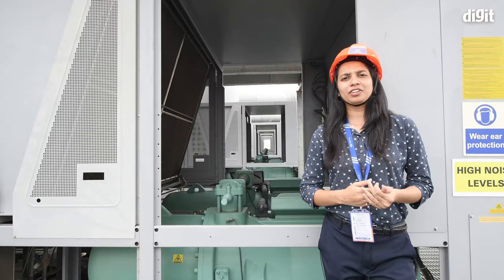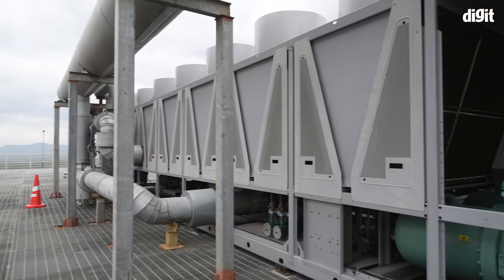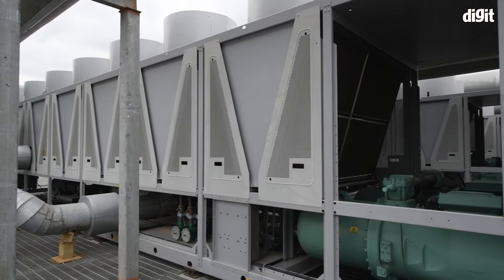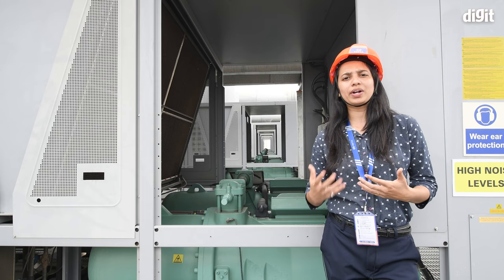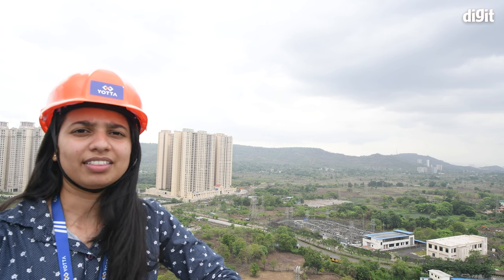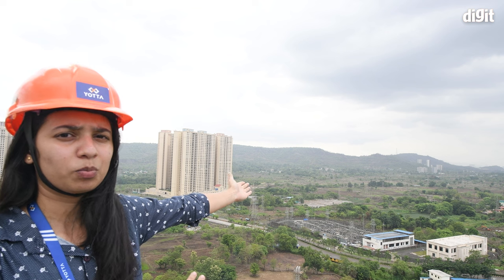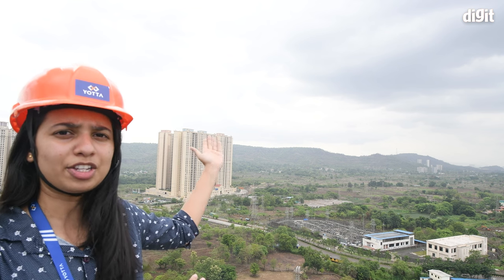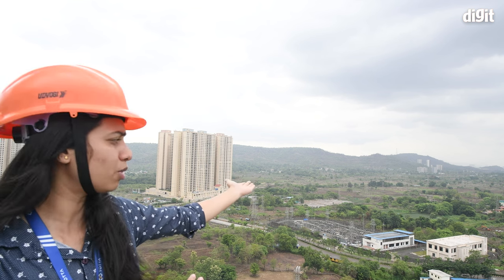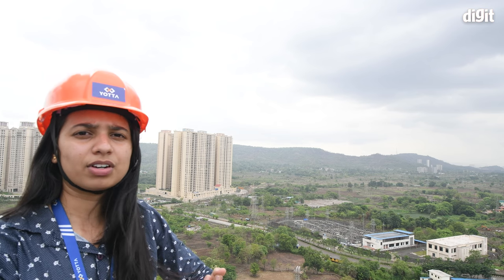We are now on the chiller platform. The chillers here are data-center-specific and have a restart time of 120 seconds. Power for all equipment comes from our own substation. We receive two power sources — from Khopoli and Chembur — brought down to 11 kV at the substation, providing N+N redundancy for power supply to the building.